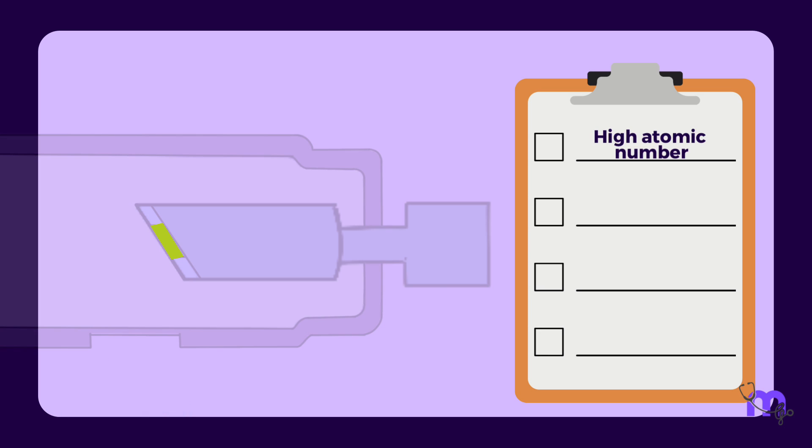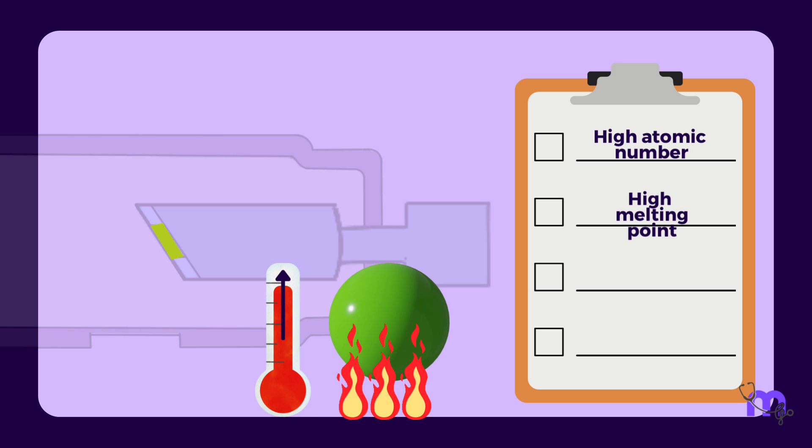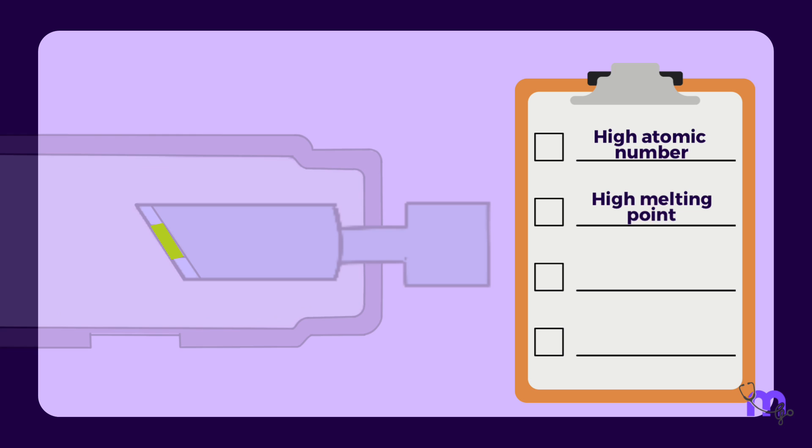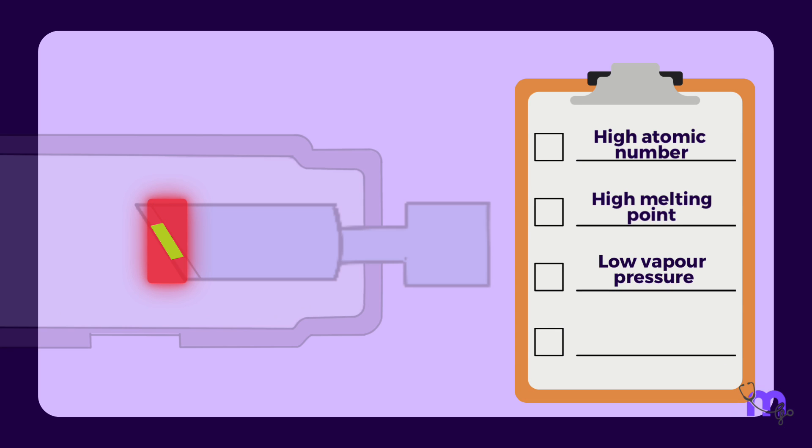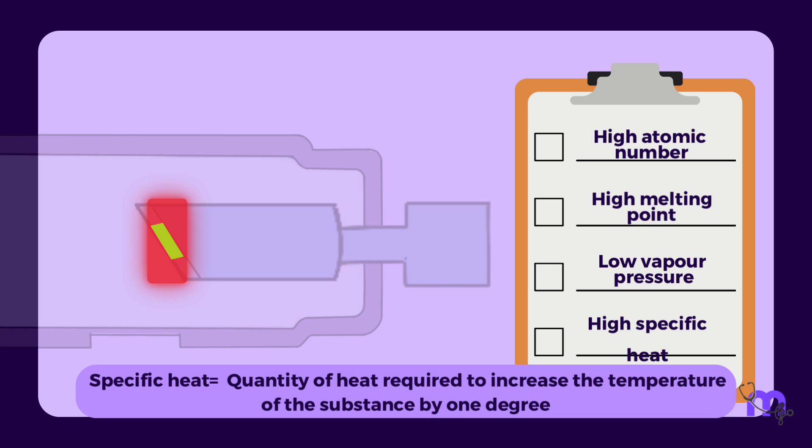Second, it should have a high melting point, which means it doesn't melt at high temperatures. Thirdly, it should have a low vapor pressure, which is the tendency of a material to change into a gaseous state, so that the target material doesn't evaporate at high temperatures. And lastly, the target material must have a high specific heat. This refers to the quantity of heat required to increase the temperature of a substance by one degree. A high specific heat will help aid heat dissipation.